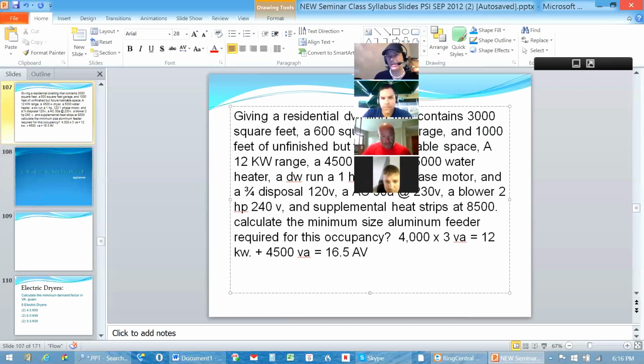In just a random house. I mean, even a 5-family or 6-family dwelling with 4,000 square feet, the chances are 16.5 is not that much, I don't think. Let's see, 16.5, just out of curiosity, divided by 0.240. You're looking at a total of 70 amps, right? And we're just talking about the lights and plugs. We're not talking about air conditioning or heating or any kind of a range or dryer. We're just talking about the lights and plugs. 70 amps worth of power? Not even close. I probably have every light in the house that I can have. So my point is that we're going to derate these.